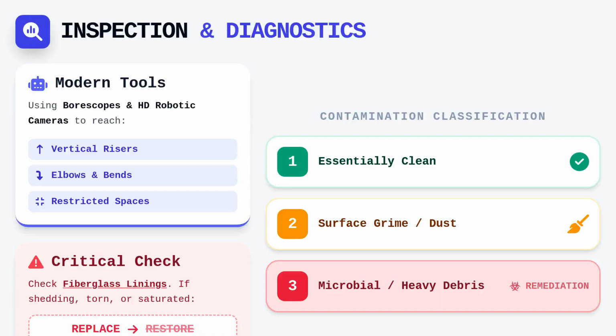To execute these inspections effectively, you must rely on modern diagnostic tools that allow you to reach areas otherwise inaccessible to the human eye. Borescopes and high-definition robotic cameras serve as our eyes inside the ductwork, allowing us to inspect vertical risers, elbows, and restricted spaces without dismantling the entire assembly. When navigating these spaces, pay particular attention to the internal condition of fiberglass linings. If the lining is shedding, torn, or saturated with moisture, it might be impossible to clean, potentially requiring replacement rather than restoration.